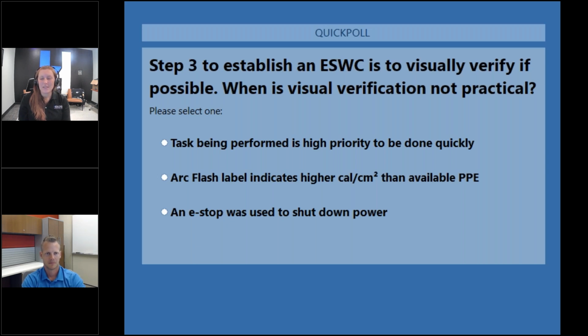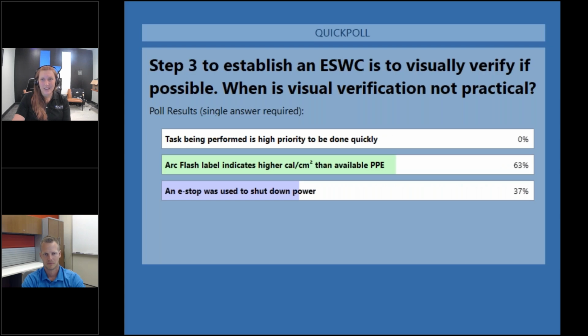Okay, starting to get some responses here. Give it just a couple more seconds. All right, so most of you got it right. If you don't have PPE rated high enough to open up an enclosure to look at the disconnecting points, you're probably not going to be the one to open it and visually verify. So maybe you need to get someone else to help shut it down if you're worried about condition of equipment, if you're worried about not being able to visually verify. Otherwise, you can just move on.